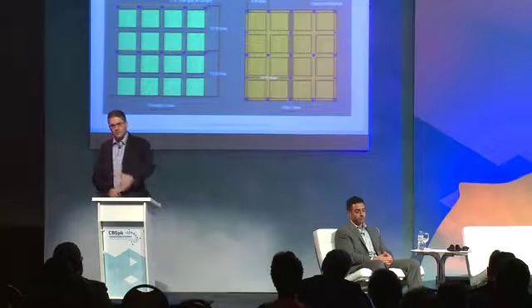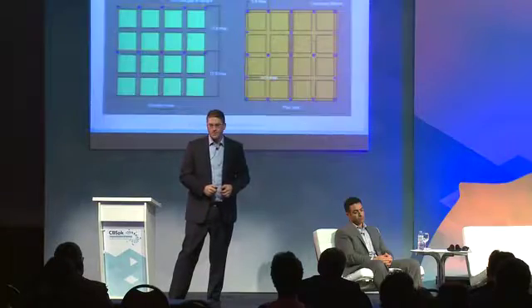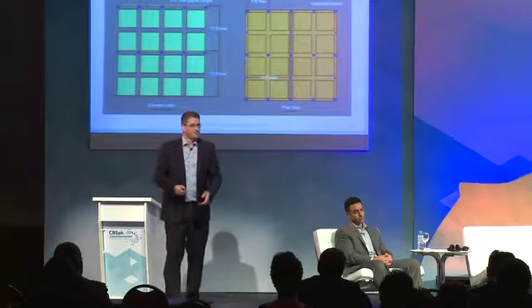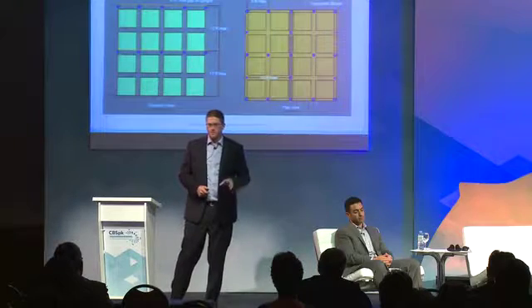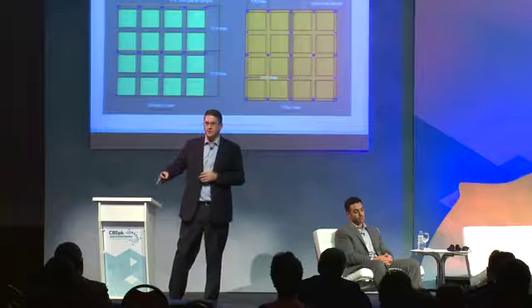Multiple row racks do a repeating pattern. Full lines with sprinklers between every pallet load, alternating with lines between every other pallet load. So what's the key to this? It's good protection. It protects all kinds of commodities. The water demand is very reasonable. The downside from an installer standpoint and end user standpoint is that's a lot of sprinklers.